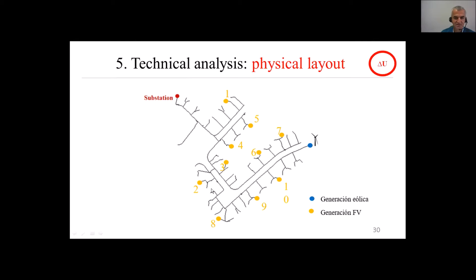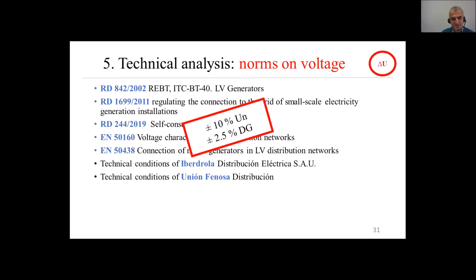Summarizing the results of the analysis of these norms, we concluded that the influence on voltage from distributed renewable energy production should not be higher than 10% of the nominal voltage, and not higher than 2.5% at the transformer output. So there are two limits: 10% over the nominal voltage across the distribution grid, and at the point of connection to the substation transformer, the influence should not be larger than 2.5%.